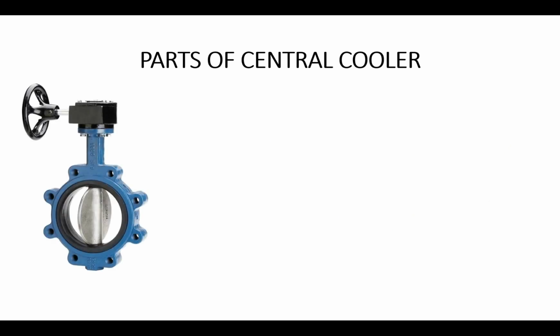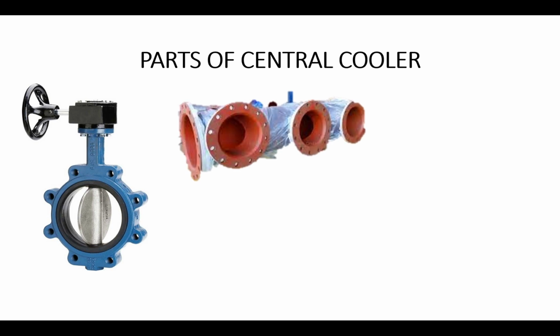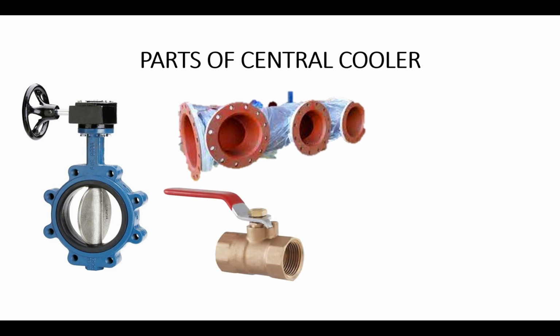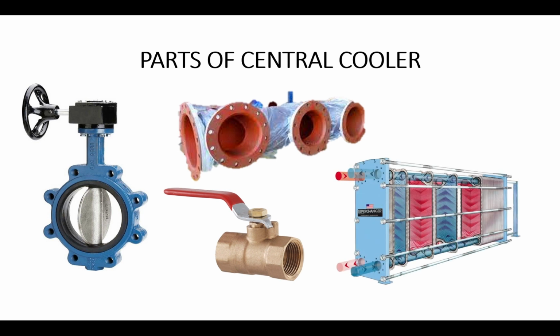Parts of the central cooler. Butterfly valves are installed at the seawater inlet and outlet as well as the fresh water inlet and outlet. The piping is coated with rubber on the seawater side to protect the pipe from corrosion. Ball valves are installed as vent valves and drain valves on the seawater and fresh water sides. The heat exchanger consists of a series of plates for heat transfer.